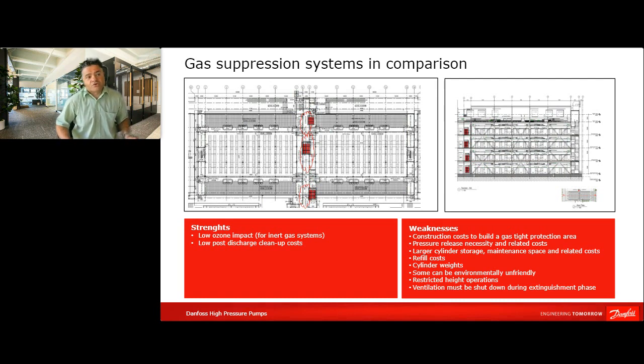The next one is that once you have distributed this gas agent into those rooms, you overpressurize the room. So in order to avoid any structural deformations or any damage of the building materials, you need to provide sufficient pressure release openings inside your construction. This is also an architectural compromise that you have to consider, which you don't need with the high-pressure water mist system, because the water mist that comes out of the nozzle is at atmospheric pressure, and you don't overpressurize those rooms.